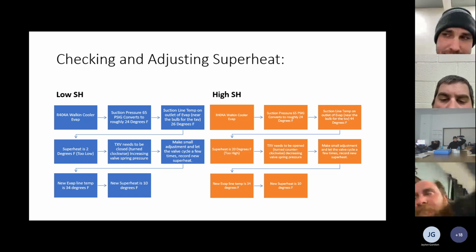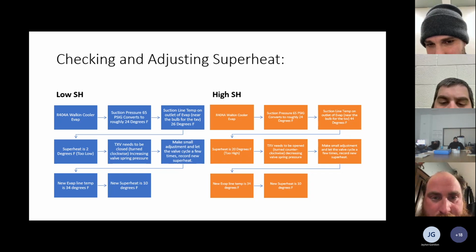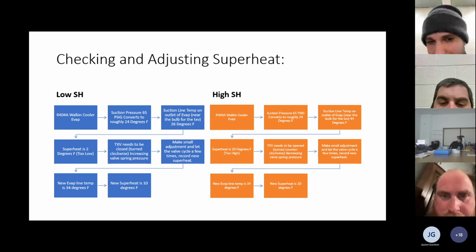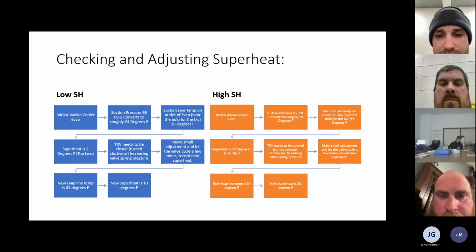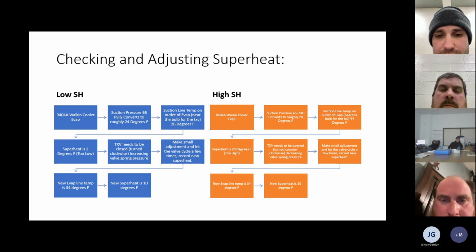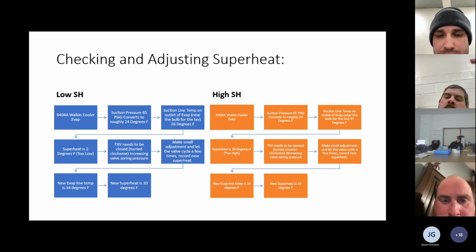So that'd be kind of like when we didn't see the ice on the very bottom of the evaporators at first, and we were trying to set superheats. We didn't notice that little layer, and it was causing a big issue. Well, that's because ice on a coil like that acts like insulation, so it's not going to pick up any heat. It's not going to change state, from a liquid to a vapor like it's supposed to. So that's why you want to make sure the coil's clear.